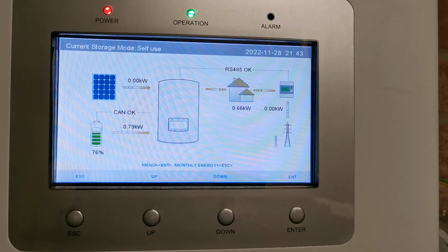Secondly, if you choose to set the export power limit to 0, as in you do not want to export anything at all, the inverter tends to err on the side of caution, so you end up importing a little bit more than you would if you allowed a tiny bit of export, as the inverter is always trying to stay on the safety side and not allow any export at all, so that tends to use a little bit more import power.